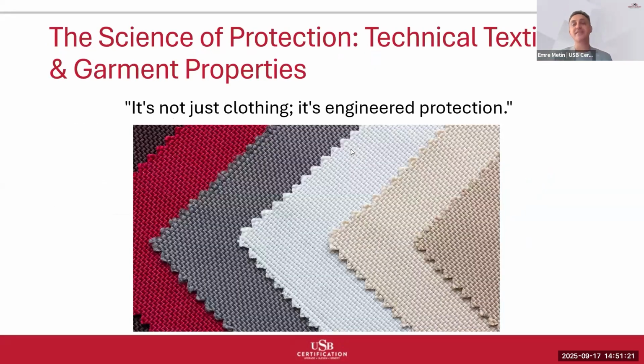The science of protection: technical textiles and garment properties. It's not just clothing, it's engineering protection. The fabric samples you see here represent different approaches to achieving flame resistance and arc protection. We call it FR and AR. Each of these materials has been engineered at the molecular and treatment level to interrupt the combustion process and provide thermal insulation. When we specify arc-rated PPE, we are not just buying work clothes that happen to be fire resistant. We are specifying technical textiles that have been designed, tested, and validated to provide measurable protection against specific energy levels.